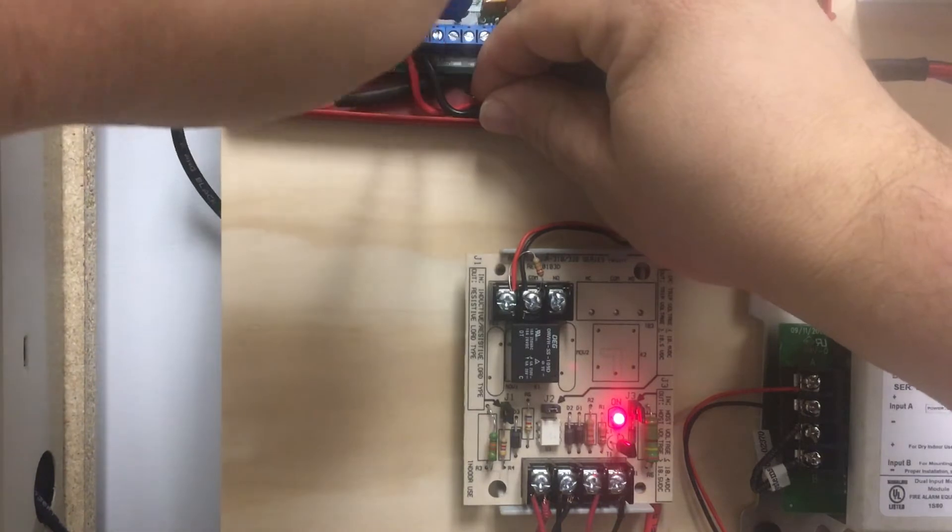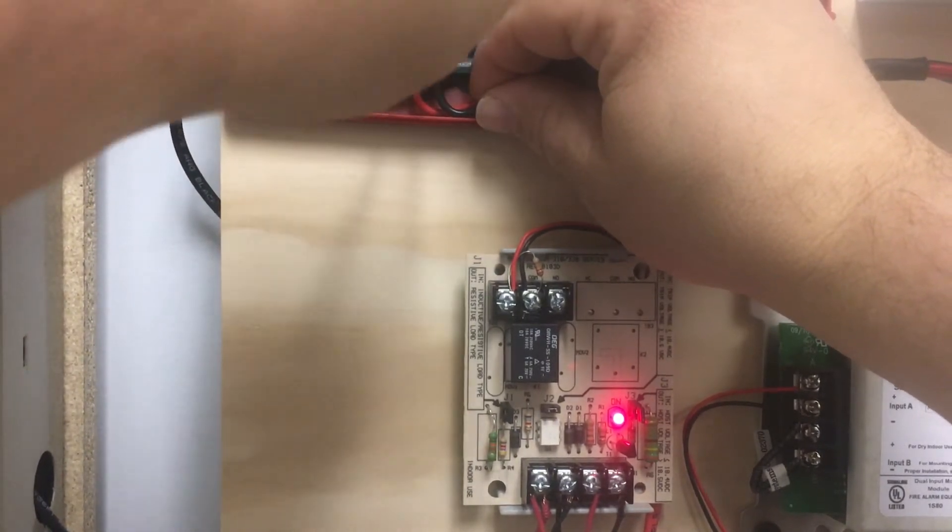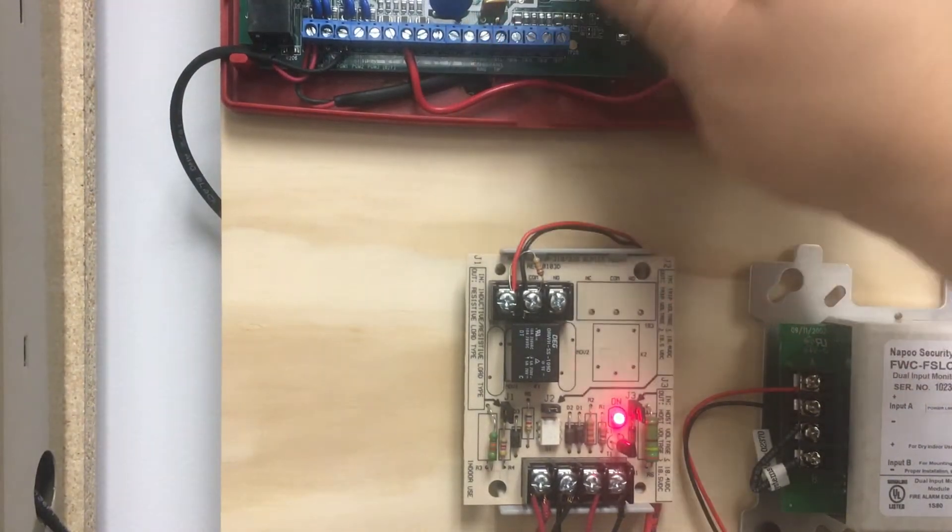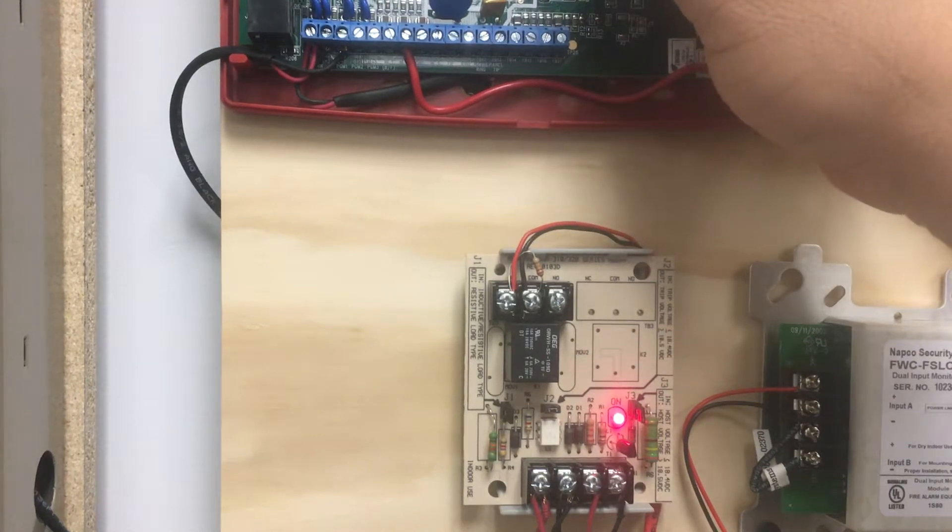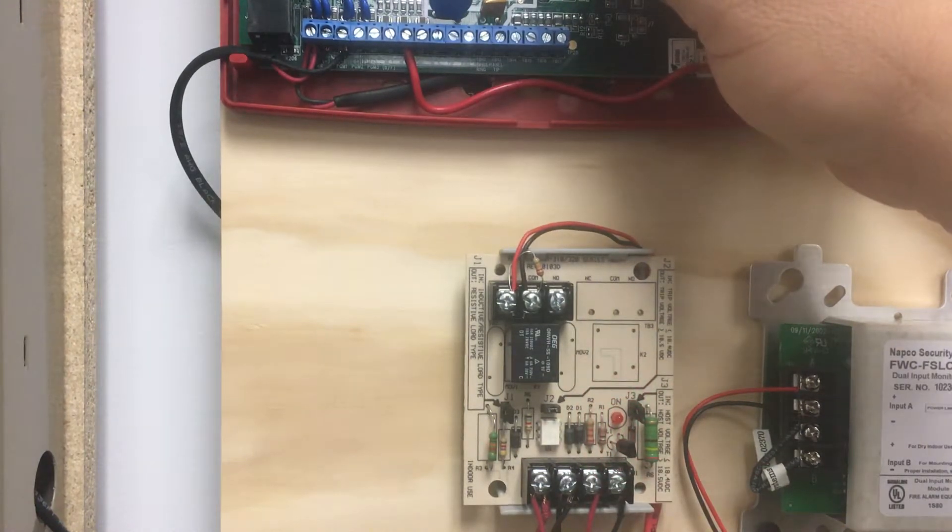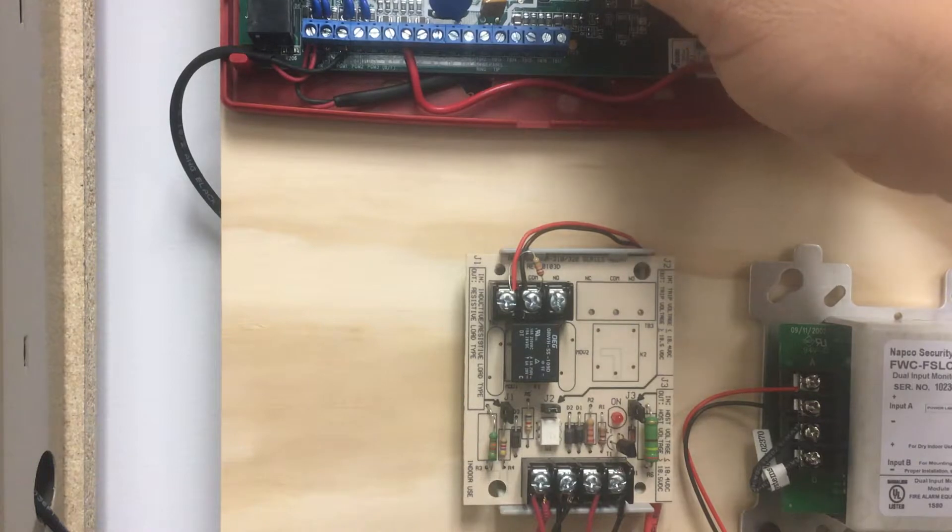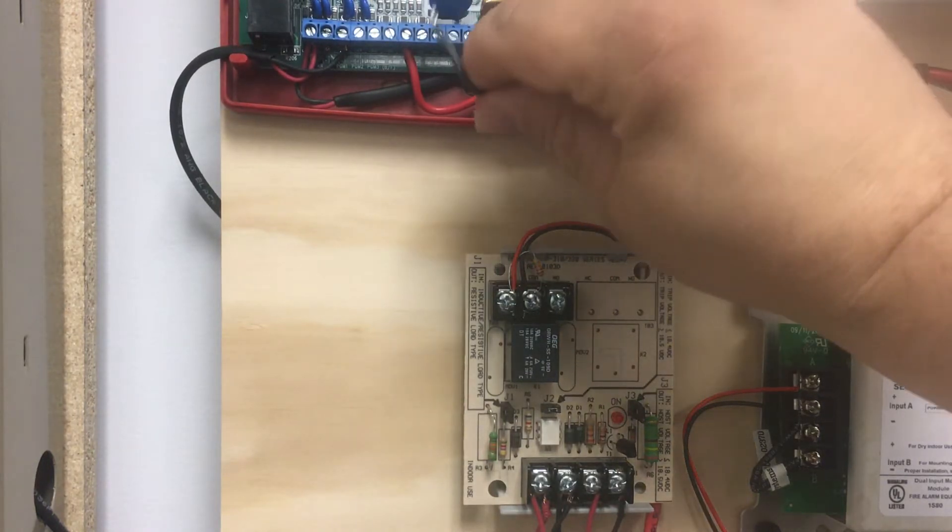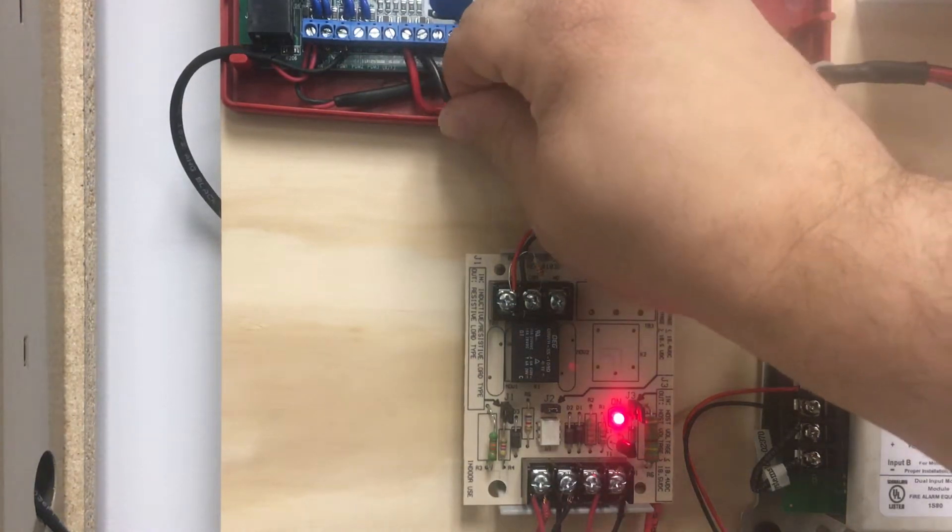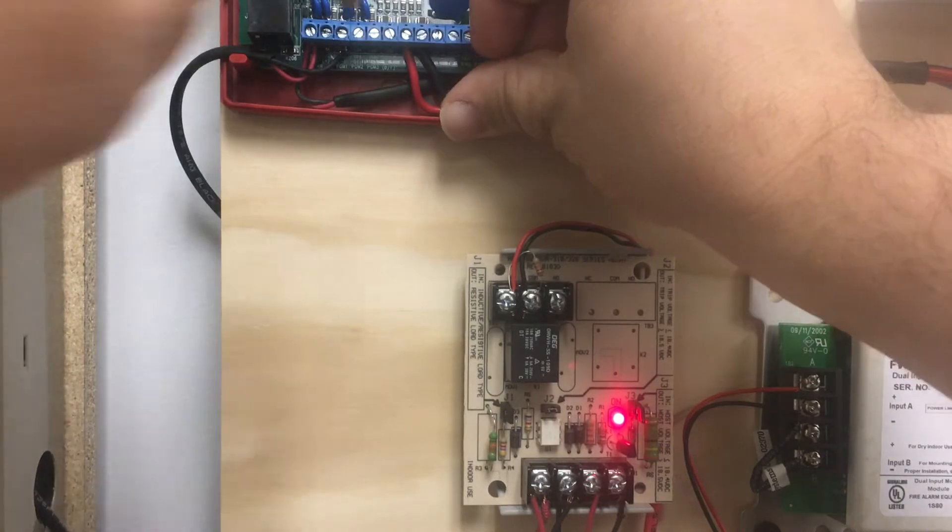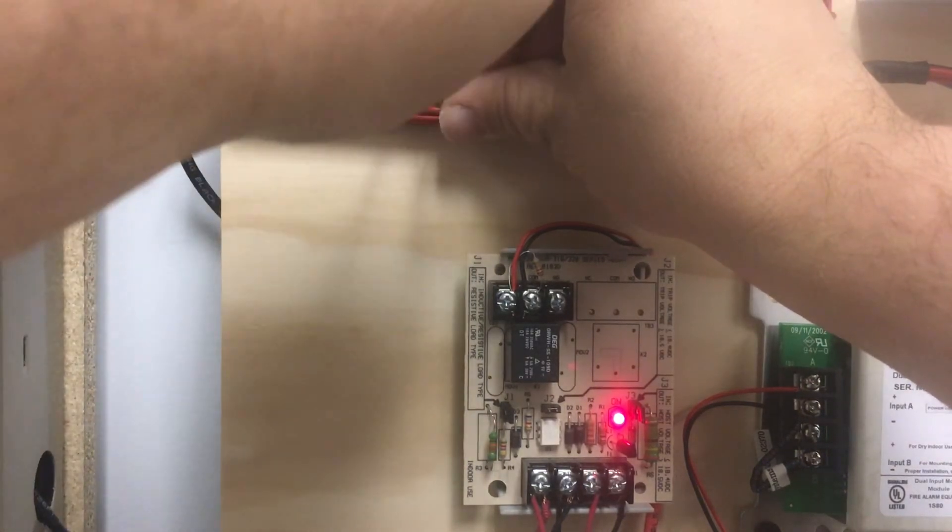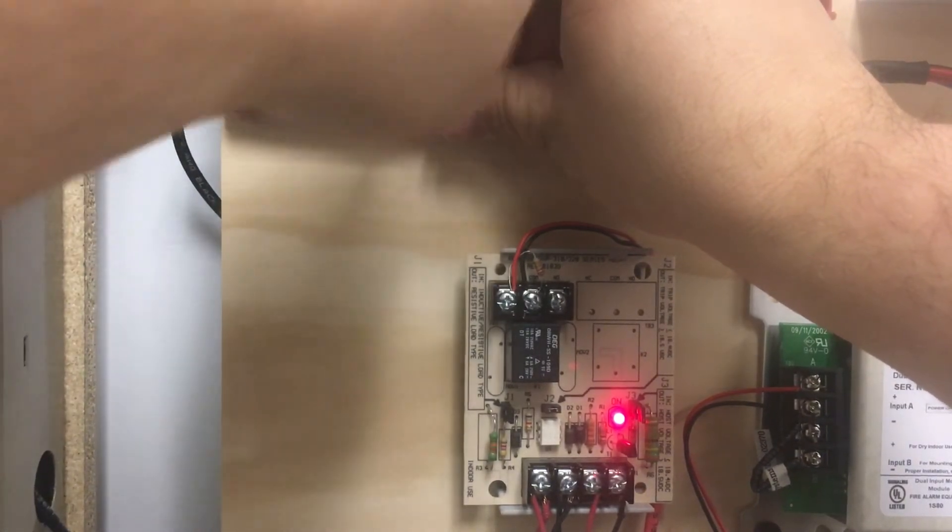So, to simulate a trouble condition, I'm going to remove my portion of my supervised wiring harness, causing a cut wires condition, and you'll see the relay powers down, which would in turn trip the module, putting the fire alarm panel into trouble. And once I restore the condition, the relay will be powered back on in a normal state.